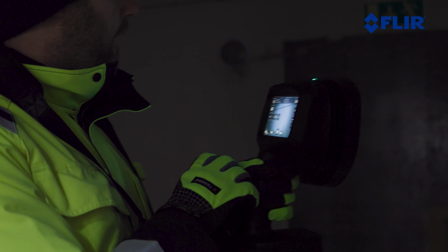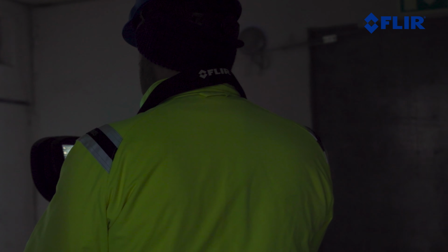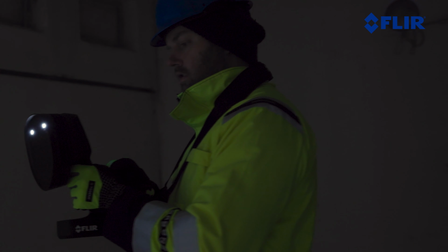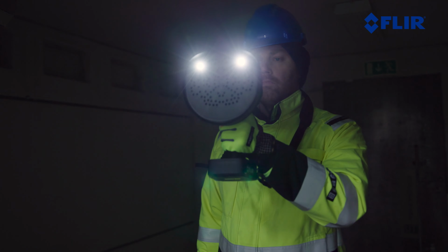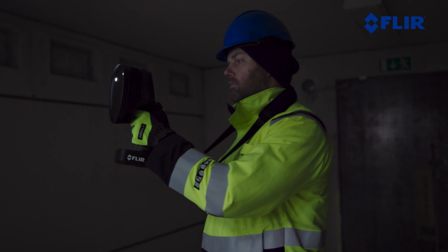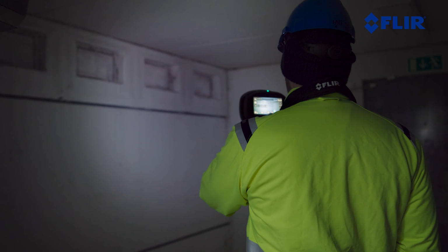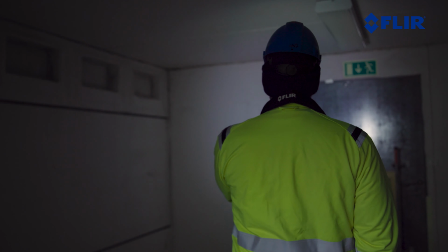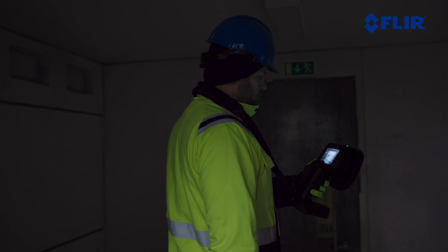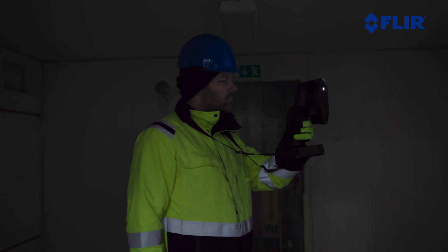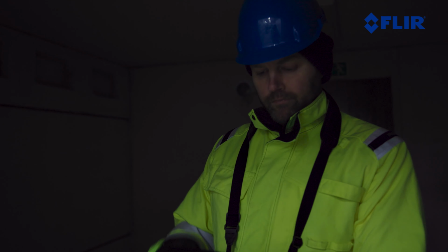The camera may sometimes show you reflections of actual sound sources that can appear at seemingly illogical places, such as in the middle of the floor. In such cases, the sound from the real source bounces off other objects. You can tell a reflection apart from an actual sound source by slowly moving the camera. If the sound source moves with the camera, you are seeing a reflection. If the sound source stays in place, this is the real sound source. Reflections are beneficial in that they indicate sound sources that are not directly in the line of sight, and might otherwise be overlooked.